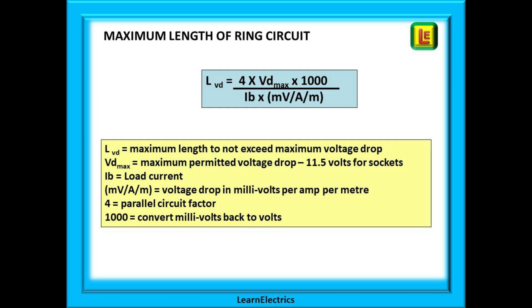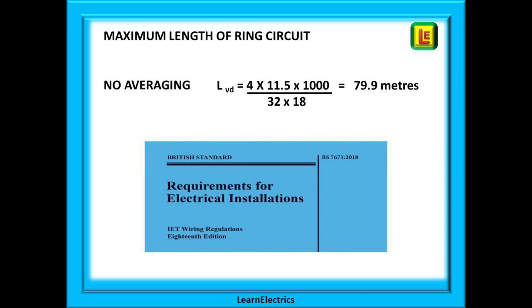If we calculate the maximum length of a circuit without averaging the load current, we will put the following numbers into our equation. You can see that we have used 32 amps, the full load, on the bottom row of the formula. Calculate this and we have a maximum circuit length of 79.9 meters. Above this circuit length our voltage drop will exceed the permitted limit of 11.5 volts.